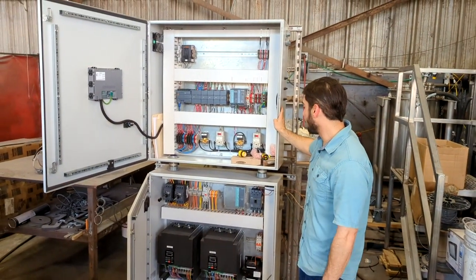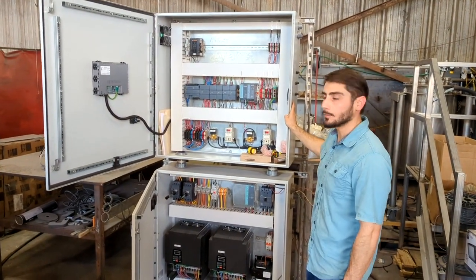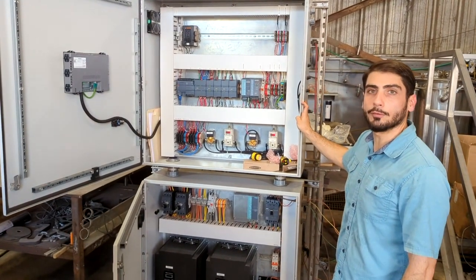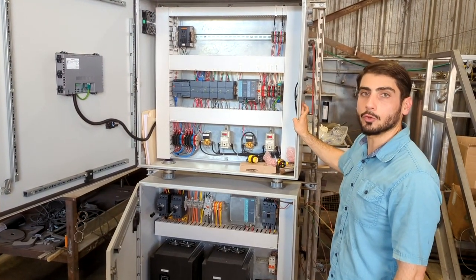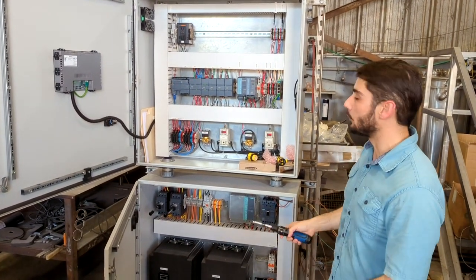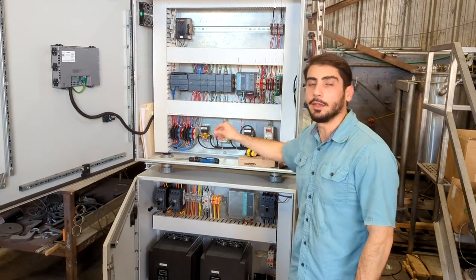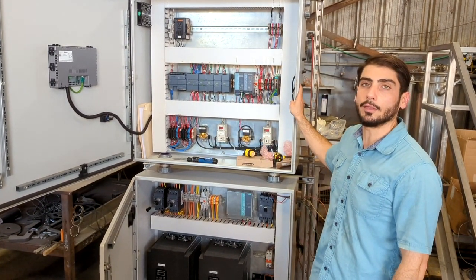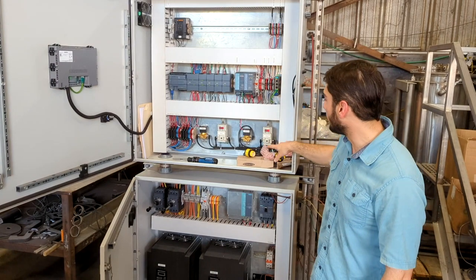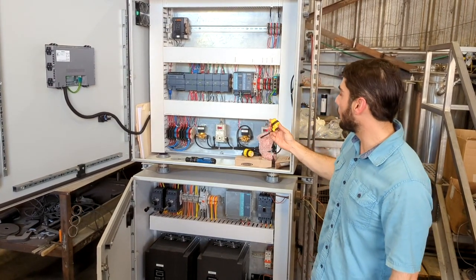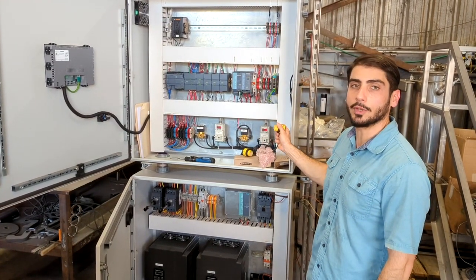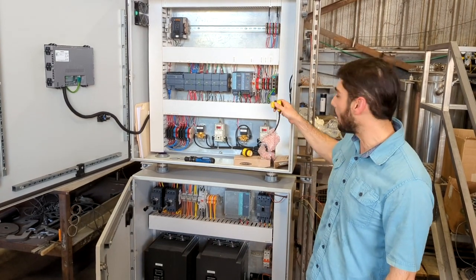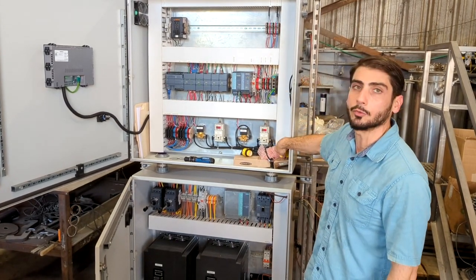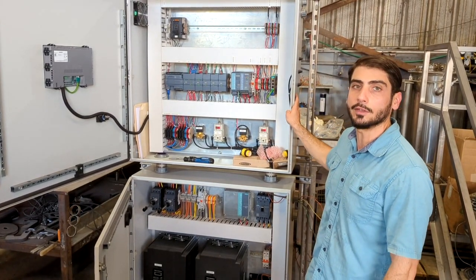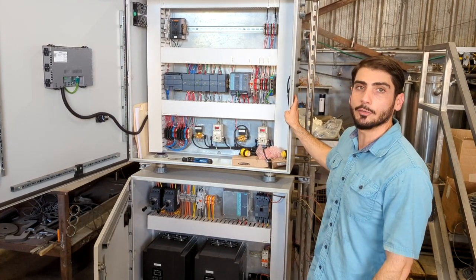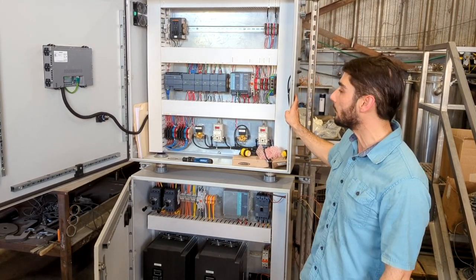What we're doing here is we have a two-press system where one press is an overflow for the other. We have some level control mechanisms that we're using to control the motor speeds. To gauge what is going on inside the level of the hopper, we're using these devices here. They're Banner radar sensors. It's a new type of technology, better than ultrasonic and other types of sensors, because you can see through steam, other gases and things that get in the way of nominal level sensors that have been used in the past.